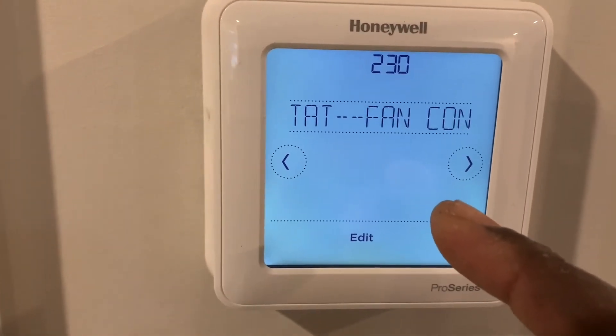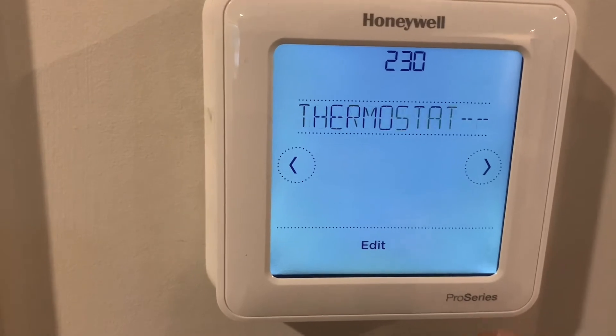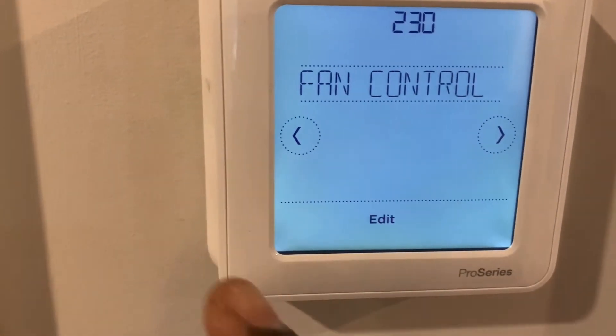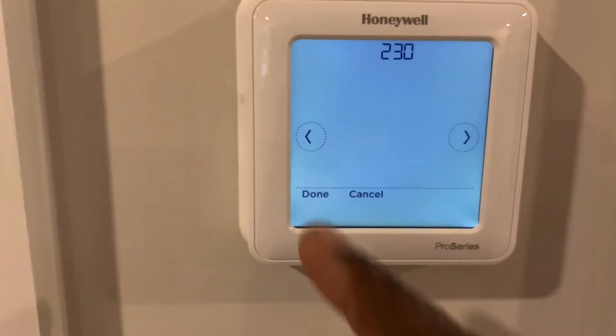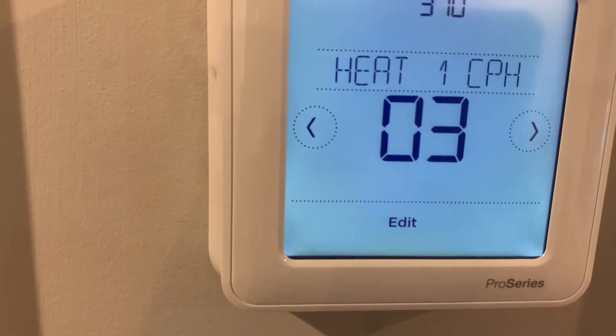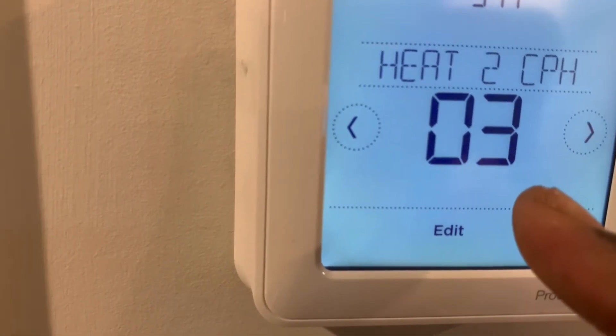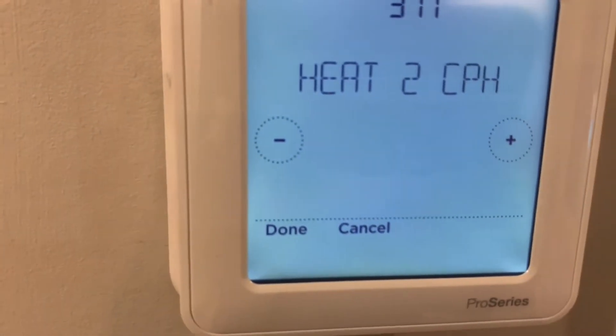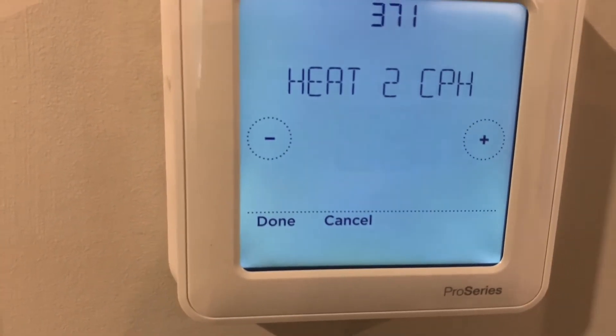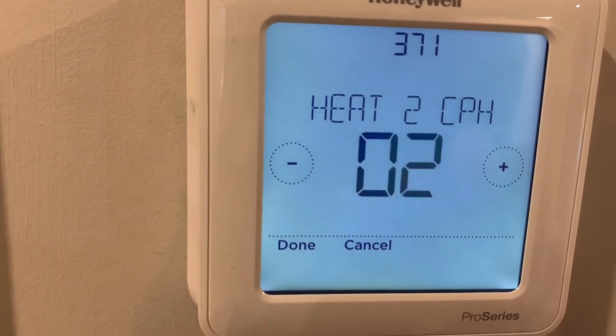Thermostat fan control — I'll leave it at thermostat control. Cool cycle per hour — leaving that as default. Heat one cycle per hour — default. Heat two cycle per hour — I'm going to lower that, because not only do I have a time delay set for 10 minutes whenever we call for second stage of heat, which is the heat pump compressor outside.